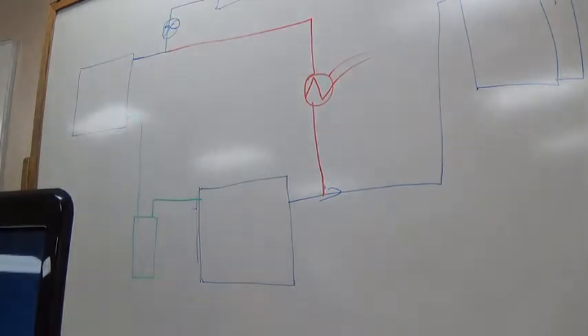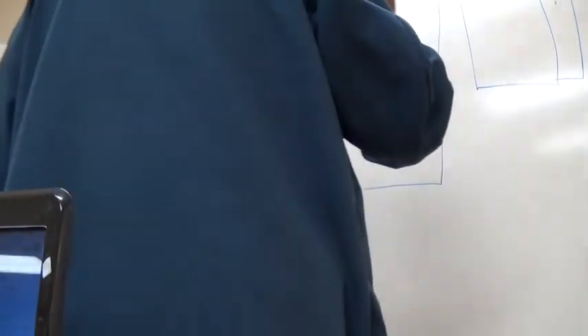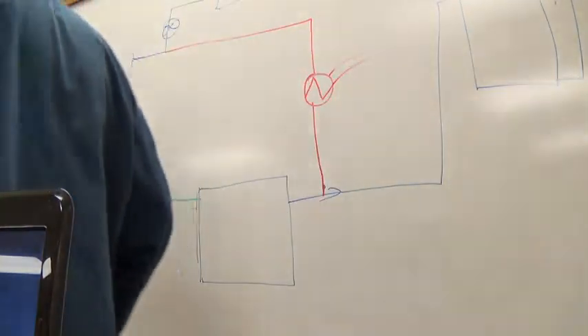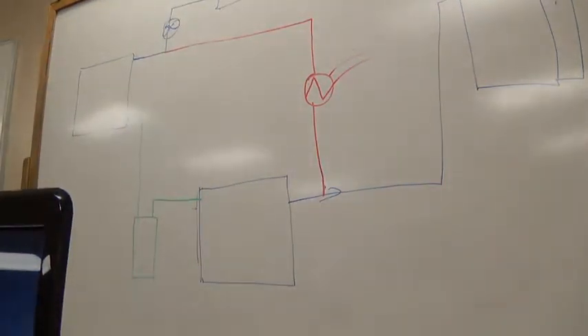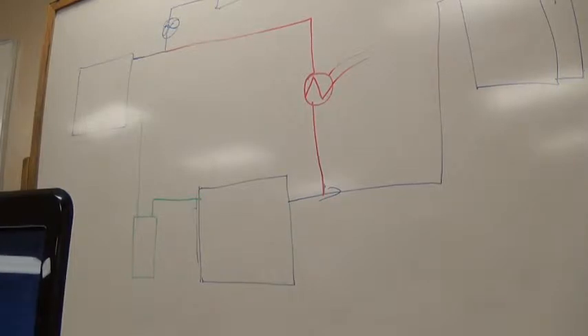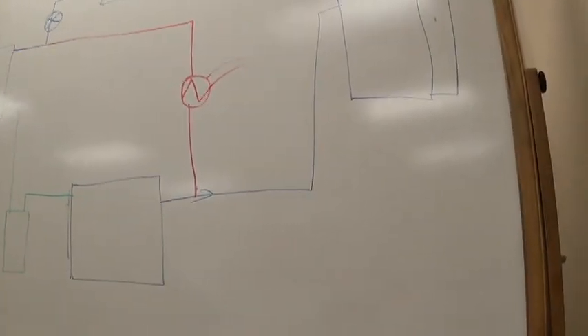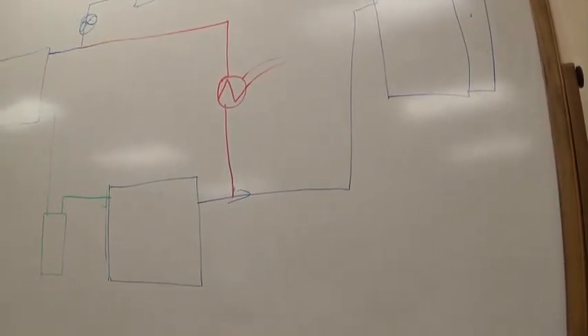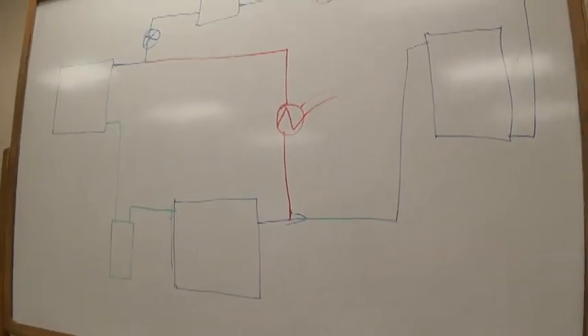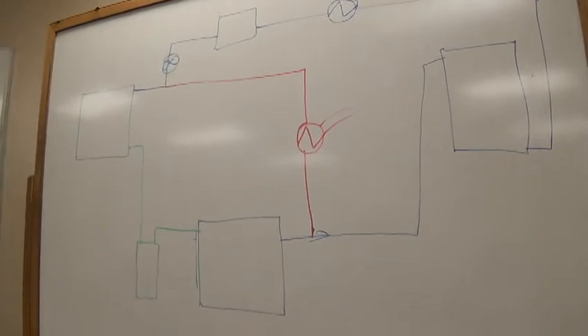If we are going on the bigger machines, you will end up having a receiver too, a liquid receiver. Small cells have critical charge in most of those systems, so they would not have a receiver or suction accumulator. But if that machine data plate says it takes 10.5 ounces, that's what it takes. You've got to weigh the charge.